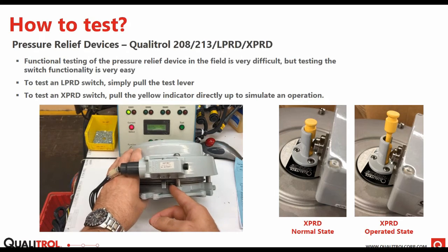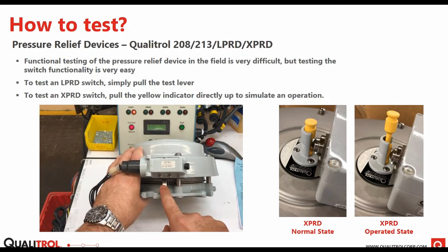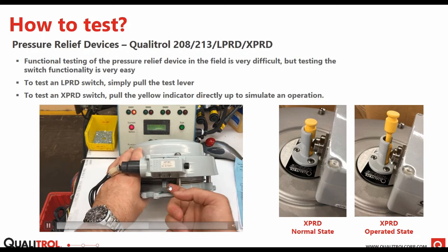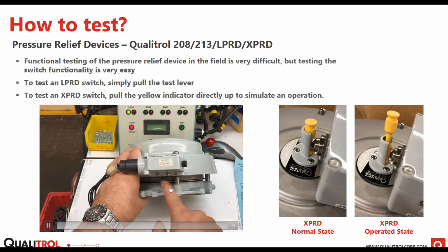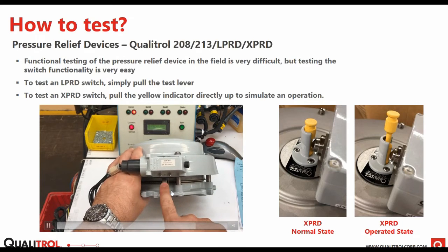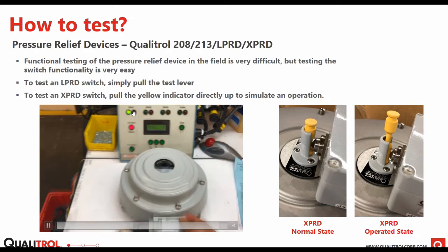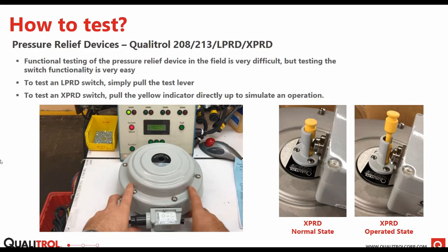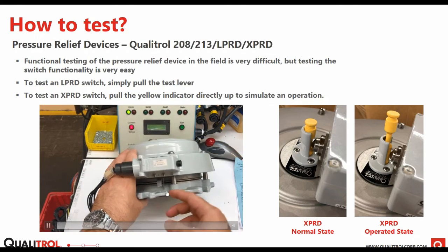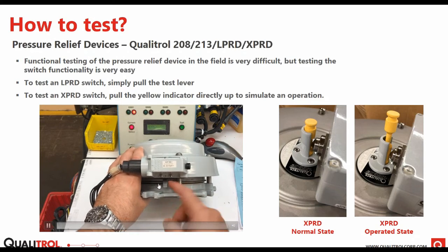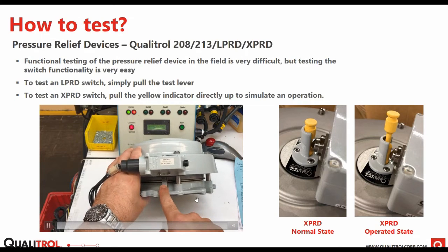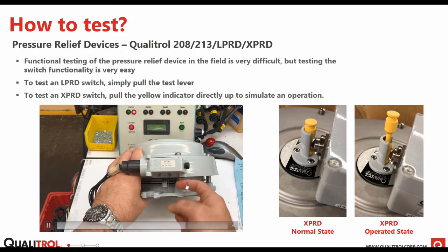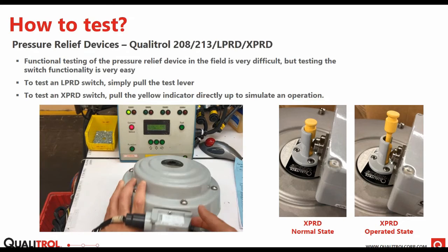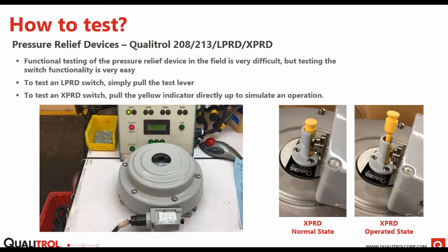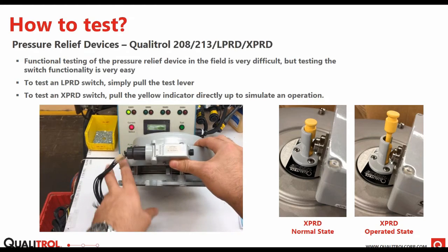The majority of our LPRD switches have this test lever here. On the right, you can see the test lever, and on the left, you can see the reset lever. What you're going to want to do is pull the test lever until you hear the switch click into place, and you can see it actuating up the top here. And then you can just reset it with the reset lever. If your LPRD switch does not have a test lever or a reset lever, this same test can be done with a screwdriver. Underneath here, you'll be able to see the little cam gear that rests on the relief plate of the pressure relief device. You can actuate that and then reset it with a screwdriver and do the same test.